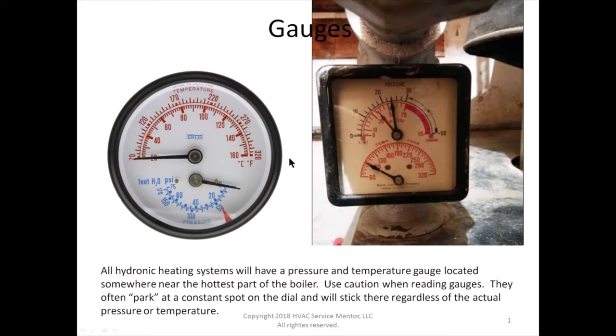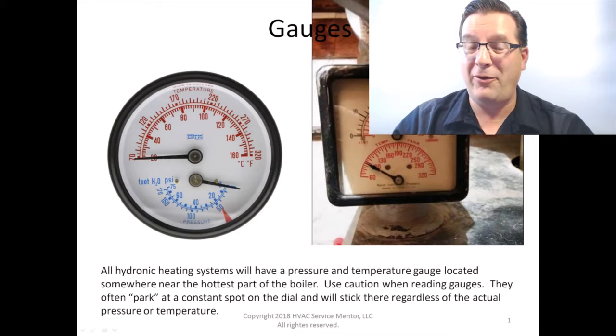It's always a great idea to have your own pressure gauge that you can screw onto a boiler drain to check the pressure independently. On both of these pressure gauges, pressure is indicated in two different ways. The gauge on the left shows pressure on the blue scale at the bottom in PSI, or pounds per square inch, and feet of water. On the one on the right, pressure is on the top, identified in pounds per square inch on the outside dial and altitude on the red inside dial. Now that is a clue — get your notebook out. We'll talk more about that later.